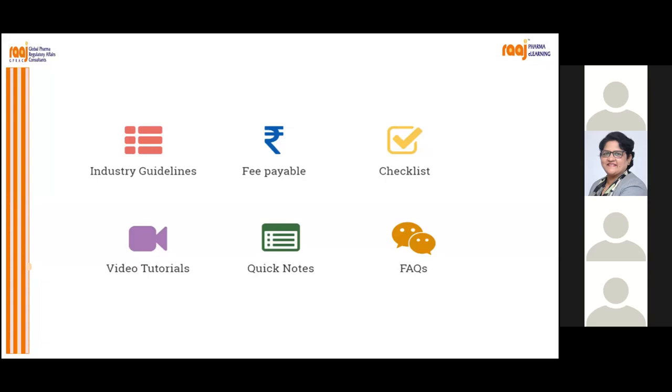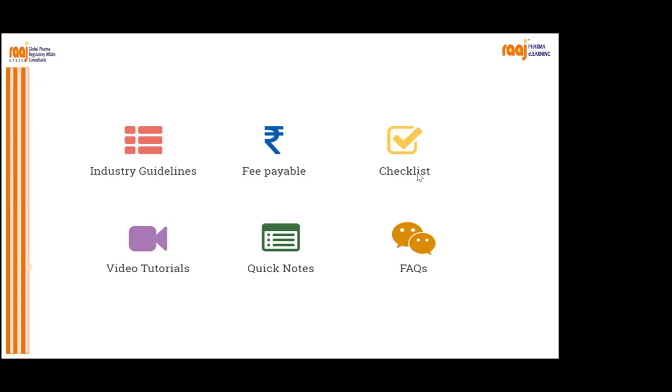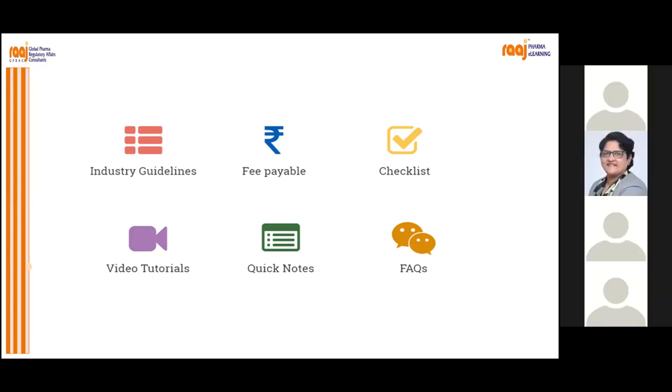Then there is a checklist. This is the most important form that we will need. The medical device rules 2017, which we spoke about in the first session, have an annexure at the bottom of those rules. So depending on your class of device and the type, if you want to import, manufacture, sell, or perform clinical investigation, depending on what your goal is, you have to select a form from the checklist. Okay. I will explain the checklist in detail in further slides.